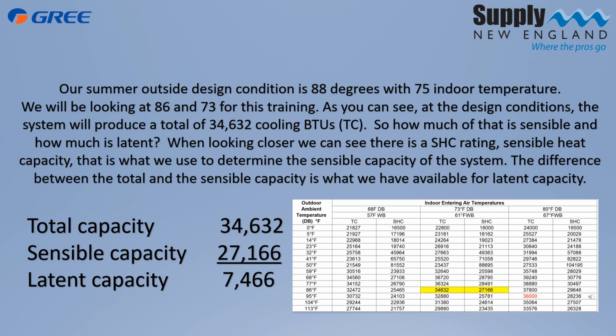Let's see what our system will do in our application. In this case, we're going to be looking at 86 degrees outdoor temperature and 73 degree indoor temperature, because that's the closest I have available on this submittal sheet. When we look at this, we'll see that there's two numbers, a TC, which is your total cooling capacity, and then an SHC, which is your sensible heat capacity. And then the difference between the two would be what we have left over for our latent capacity.